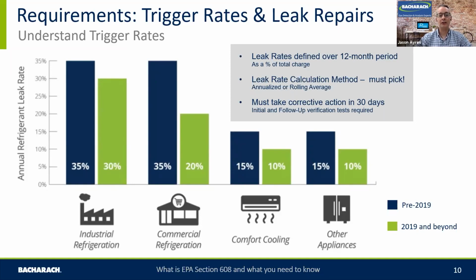So what we have here, the blue line is the older trigger rates, the green bars are for those assets, the current trigger rates. And you'll see they've come down. What the EPA are looking at is ensuring that we detect and report on leaking refrigerant sooner. So if you had a refrigeration rack that had 100 pounds of refrigerant in, and it lost 50 pounds of refrigerant in a 12-month period, it would have a leak rate of 50%. It would fall under the commercial refrigeration bracket on the chart there. And because the trigger rate is 20%, any percentage that's over and above that would mean that you have to do additional checks on that system, which we term leak inspections.